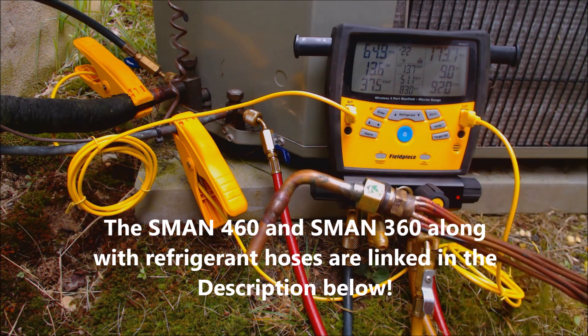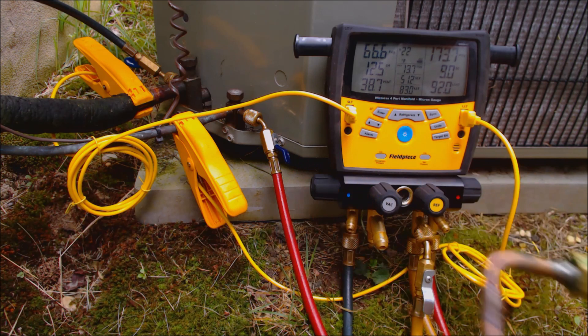Hey guys, this is the AC Service Tech, and today we're looking at how to check the refrigerant charge level on an R22 outdoor condensing unit with a fixed orifice as the metering device right in front of the evaporator coil. This is an example of capillary tubing, and this is an example of a piston chamber with a piston inside of it.